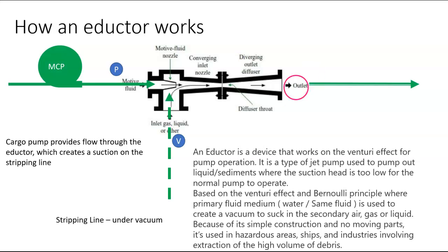So it has to be the same product. But what is nice about it is, as this tank goes dry and gets a lot of air in there, it's not going to hurt the pump at all. You can just let it suck all day long. It'll take that air, that volume out of there. It doesn't care if it's air, it doesn't care if it's liquid. So we can basically open up a stripping line and just let it go until it goes dry. And if it goes dry, so what? If it was a pump, and we were pumping it out and it goes dry, now that pump is not working efficiently anymore, and it's going to start running away from you. It doesn't have that resistance that it loves.